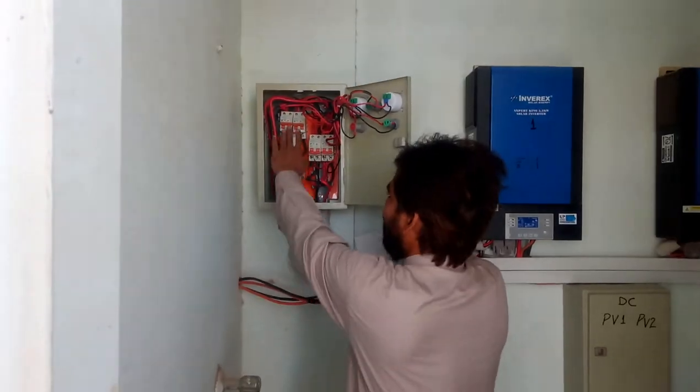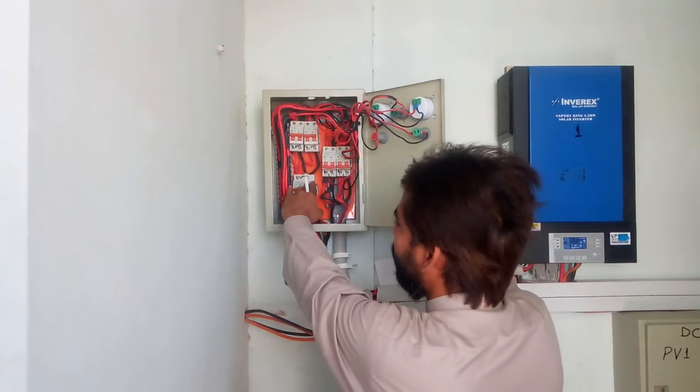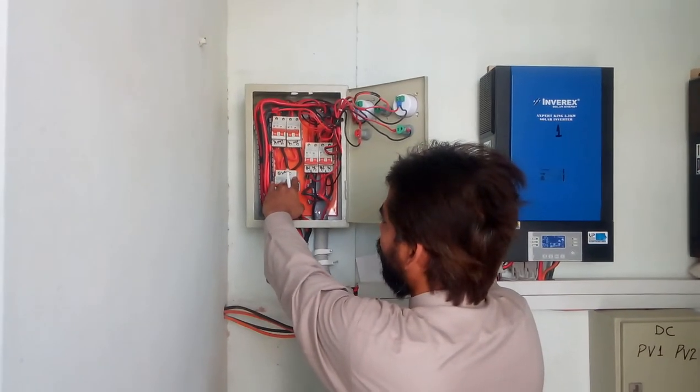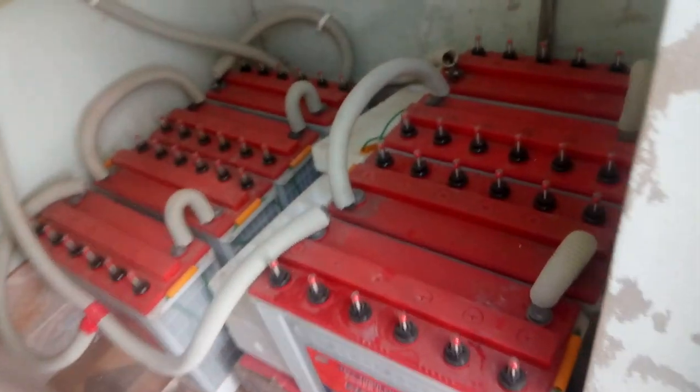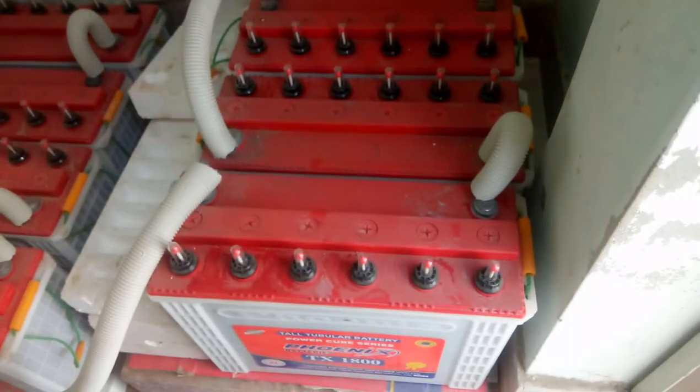We have separately put breakers in the output and we have combined it. These are our 2 breakers on the bottom of the input, and this is our battery bank. We have set it up at 48 volts and used 230 ampere hour.